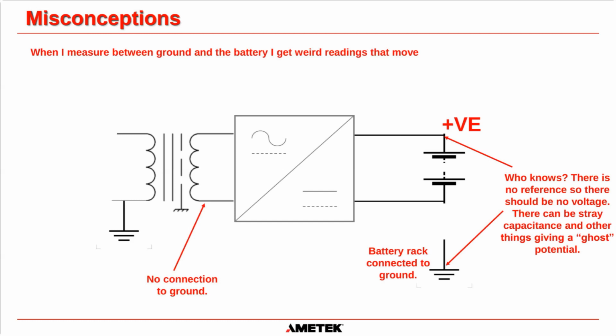If it is a value on your multimeter that then starts decreasing down to zero, then it just means your system is completely floating and you actually don't have any ground fault detection system on your charger, and you have to find the ground fault yourself. The charger is not going to tell you that there is a ground fault. Very rare these days. Most chargers come with ground fault detection circuits in them.